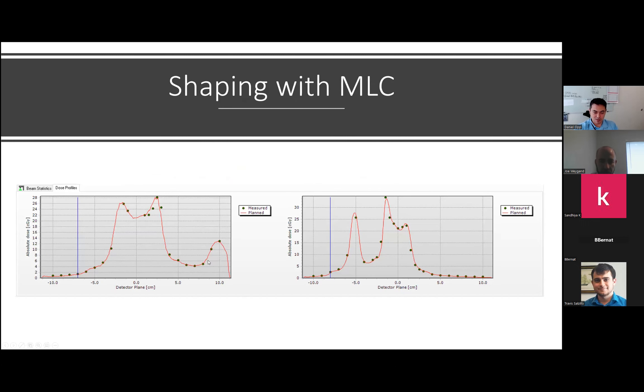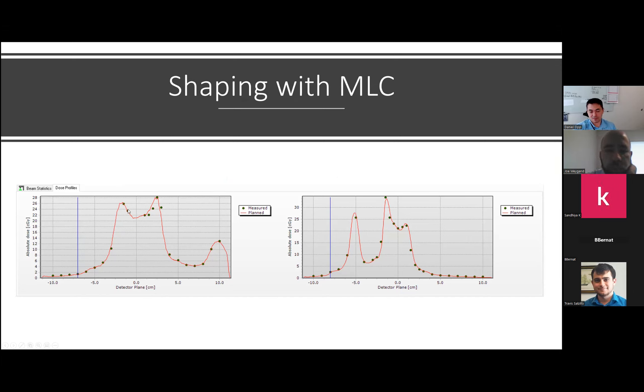Once you start using MLCs, you have a lot more control over how high or low your dose gets at specific points. This is a cross section from our Delta 4 IMRT QA device — you can see cross profiles from a single beam. If you add these up three-dimensionally across different beam angles, you can essentially deliver whatever you need to achieve your planning goals.